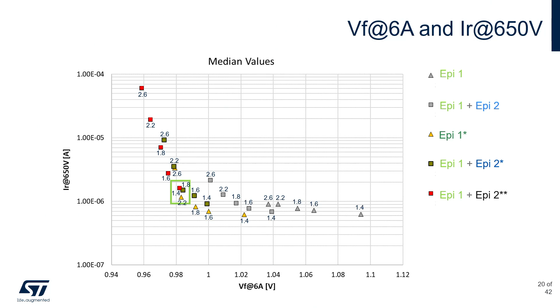But when we design our devices, we are interested not just in the VF but also in the leakage. So we plot a correlation plot of the leakage and the VF. From this correlation plot, we can get some interesting information. In this area of the plot fall the points in which there is no implant, and you can see that the leakage doesn't change so much with the pinching, while the VF changes a lot thanks to the pinching. In this area here, we find the points that have implant, in which the pinching effect plays a key role to control the leakage, but not so much the VF.